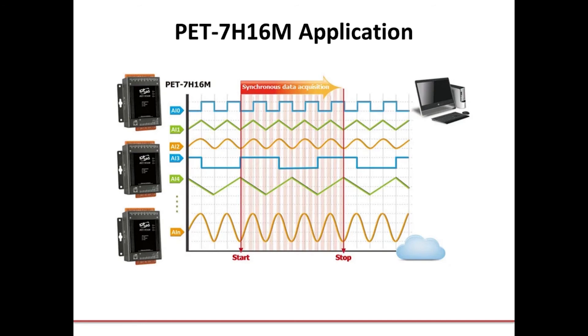In addition to the signal conditioners, you can employ one of our PET7H16M DAQ modules. These are a high-speed data acquisition module with an embedded Ethernet communication port for transferring data over the network. The PET7H16M module includes 8 high-speed analog input channels with a maximum sampling rate of up to 200,000 samples per second, which allows for simultaneous 16-bit analog-to-digital signal conversion on each channel. This module includes a synchronous data acquisition feature for each of its analog input channels — important for measuring different types of data during the same period of time under normal operation. The built-in analog-to-digital converter in each AI channel provides an anti-aliasing feature to adjust the appropriate sampling rate and filter out modulator noise.